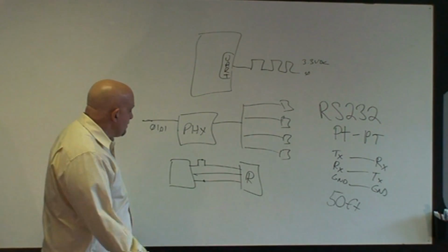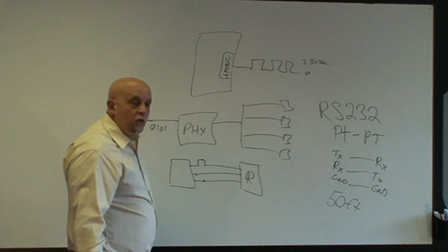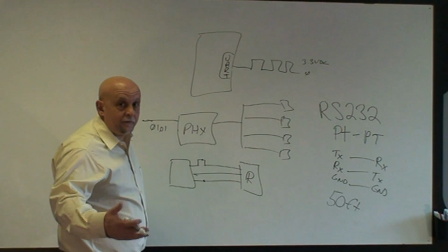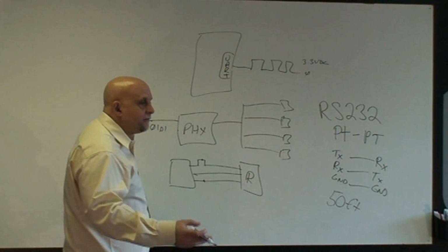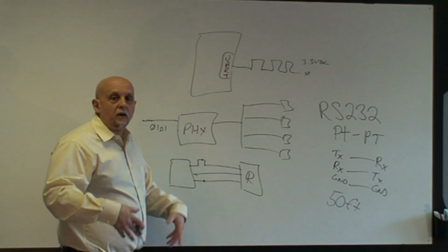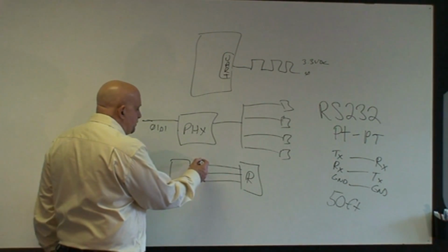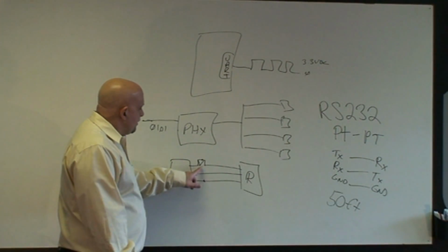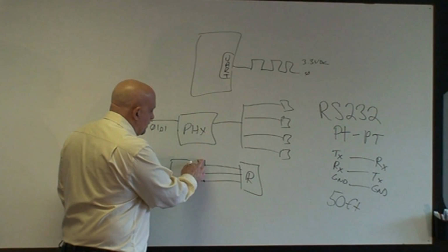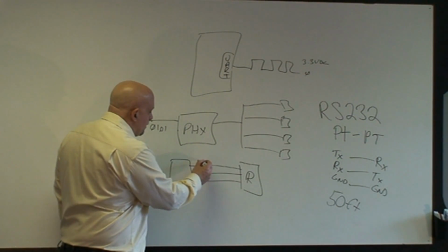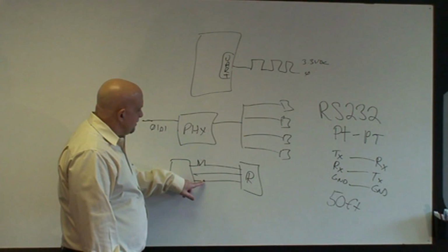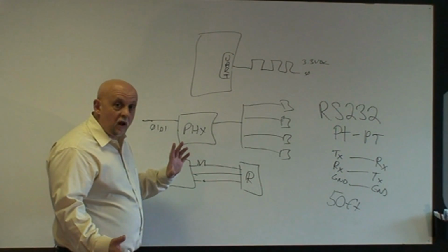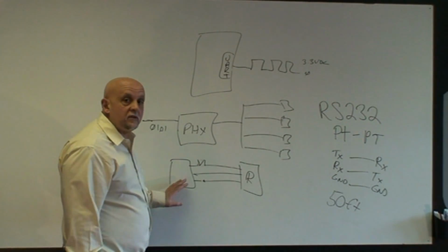What's wrong with that? Well, the problem is when you get noise. If there's a little bit of noise in this system, maybe there's a motor nearby, and in an industrial environment we're going to have noise because we have lots of things going on and off. Every time something switches on and off, there's some kind of electromagnetics. Those things get picked up by these wires, and that could force the signal down. So now it's kind of iffy. That thing that we thought was a one is now in reference to this as well. Is that going to be picked up as a one or not? Yeah, it's a problem.